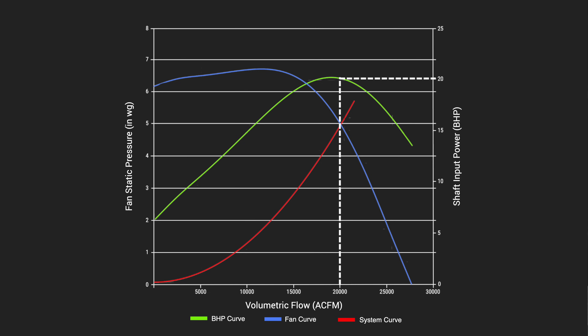At this operating point, the fan consumes 20 brake horsepower. To summarize our example, our fan is moving 20,000 cubic feet per minute while generating 5 inches of static pressure, which it needs to do to overcome the system's resistance and deliver the airflow. And to do all of that, the fan consumes 20 brake horsepower.